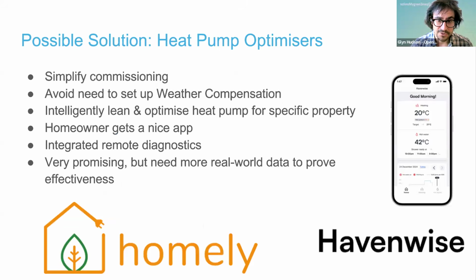A possible solution to this problem of commissioning is heat pump optimizers. And these are not to be confused with on-off third-party controls. Heat pump optimizers integrate deeply with the heat pump and automatically adjust the heat pump to work well in a specific property. They'll automatically adjust things like the weather compensation, so they avoid the problem with incorrect weather compensation being set up during the commissioning.